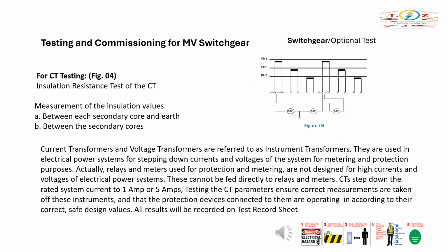CT testing, as shown in the arrangement drawing. Insulation resistance test of the CT. Measurement of the insulation values: A. Between each secondary core and earth. B. Between the secondary cores.